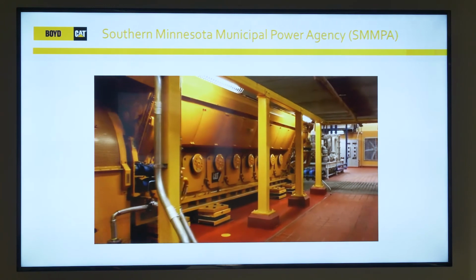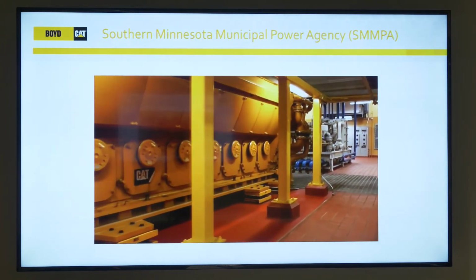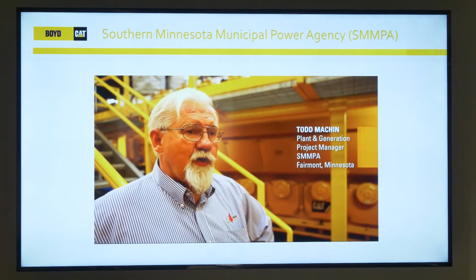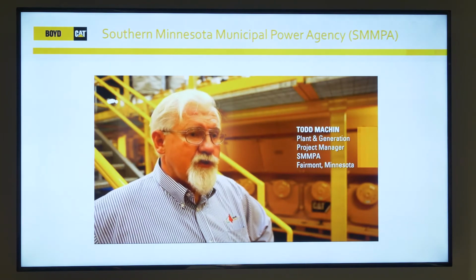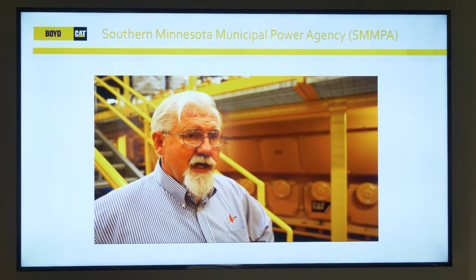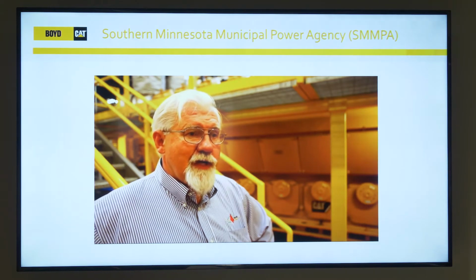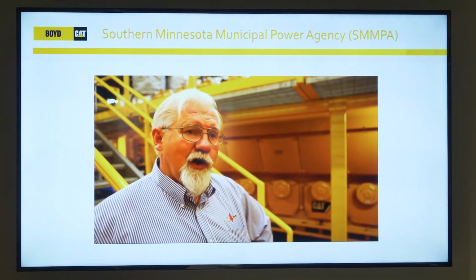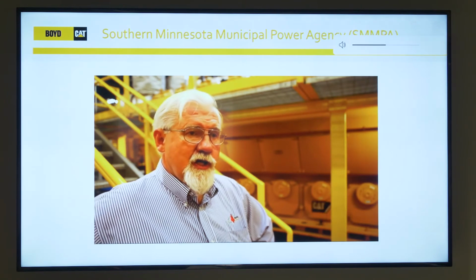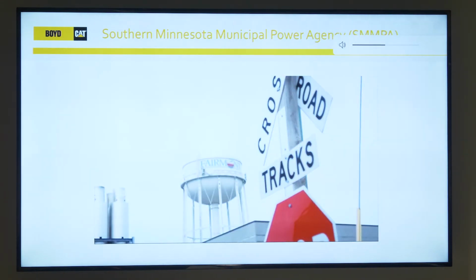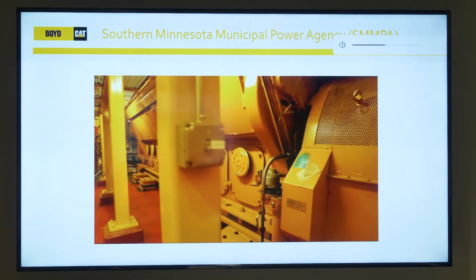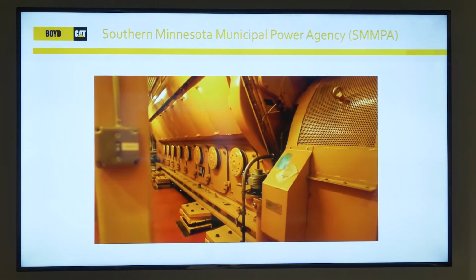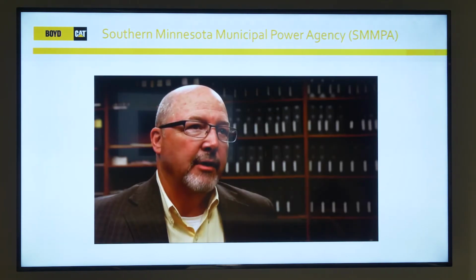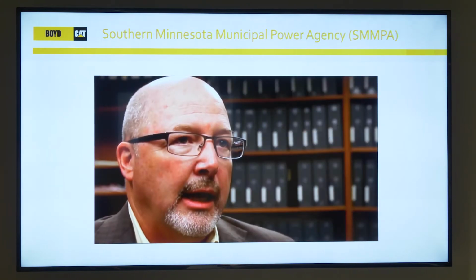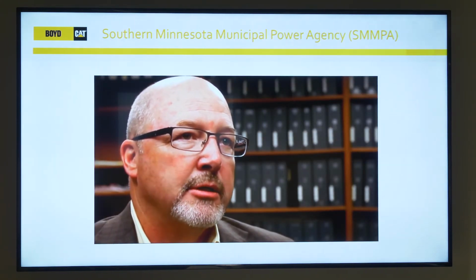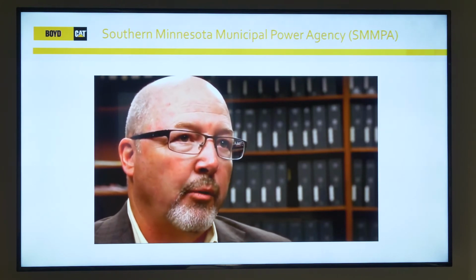The generation market has changed dramatically in the past several years to one that requires equipment that will start fast, load fast, and maintain efficiency at varying loads. We had a need to fill an intermediate level of generation, something that fit our needs. In the case of Fairmont, that was 25 megawatts, and the reciprocating engines from CAT fit that profile very well.